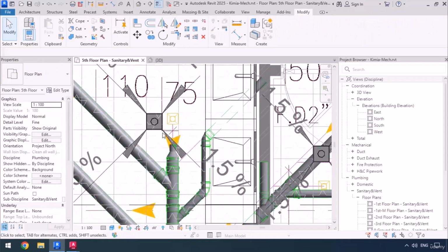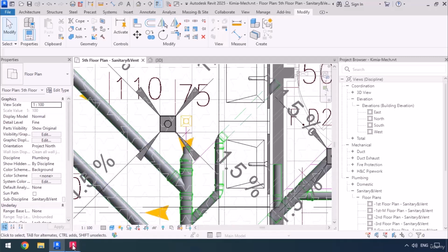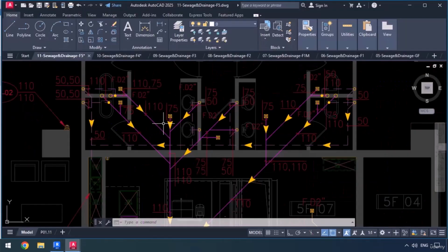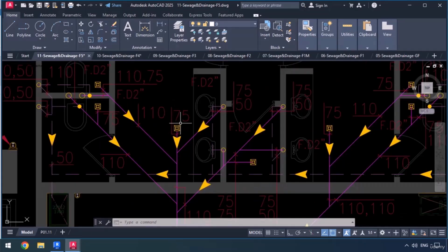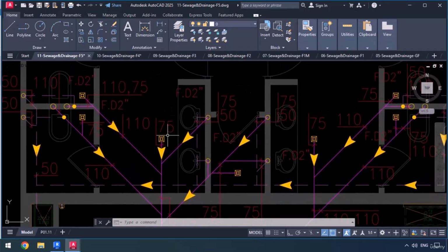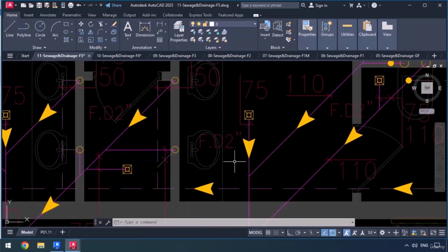Now next, to connect a pipe to this floor drain, first let's go double check in the CAD plan. So let's go over here. And you see the pipe that's going to be connected to this floor drain, it says the diameter is supposed to be 75. But as for the floor drains themselves, we've got a little tag next to the others. For example, this one says FD 2 inches. Floor drain 2 inches, which would be 50 millimeters, whereas up here it says 75.